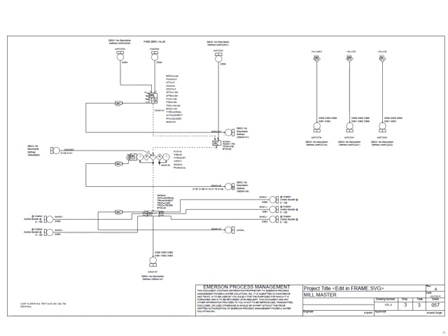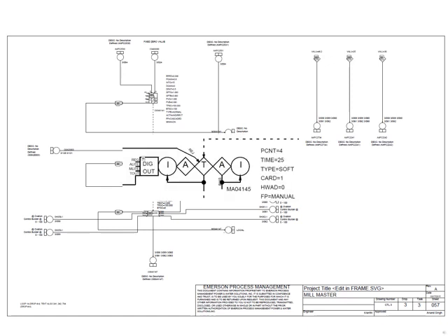This is a MA station algorithm. It interfaces a CRT-based soft manual auto station and an optional Ovation loop interface module card with the functional processor. There are three available modes: the auto, manual, and local. There are three types of this algorithm field depending on configuration. It may be auto manual station only. It can be Ovation loop interface module or a valve position module.